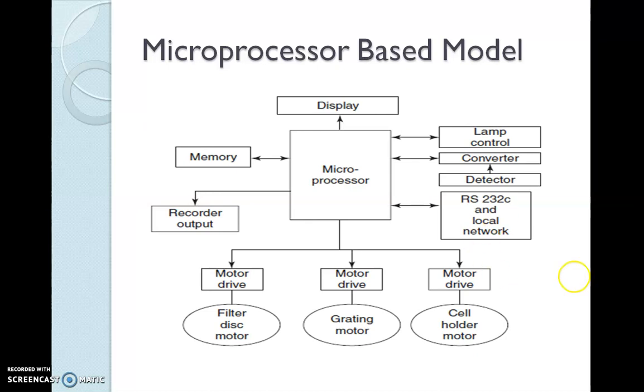This is the basic block diagram of a microprocessor based spectrophotometer. The diagram shows only the post detector electronic handling and drive systems, all controlled via a single microprocessor. Once the operator defines parameters such as wavelength, output mode and relevant computing factors, the system automatically ensures the correct and optimum combination of all the system variables. That is the special case here.